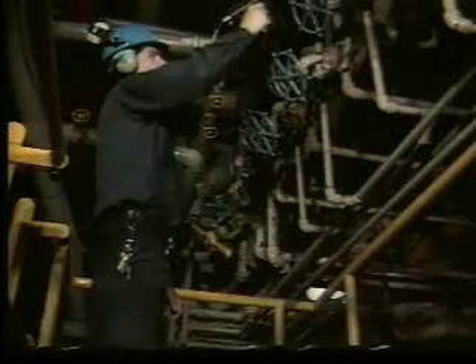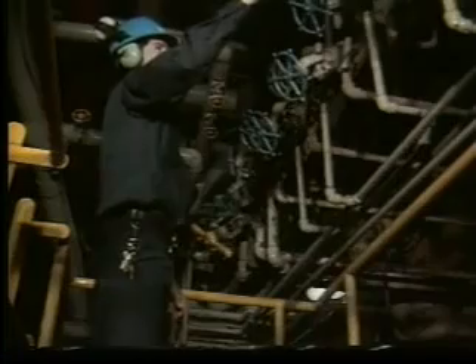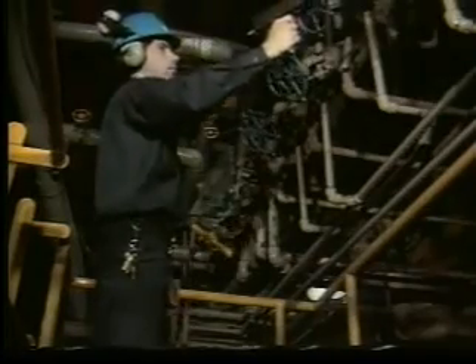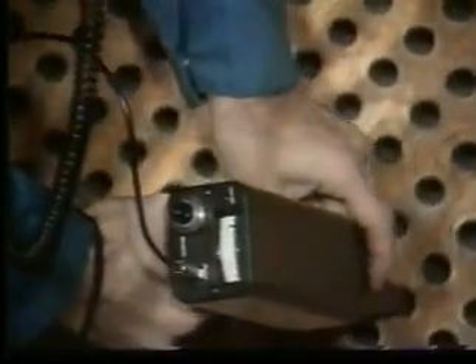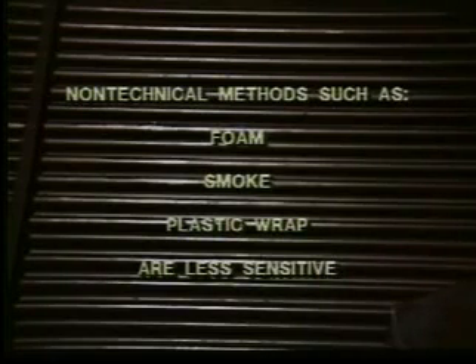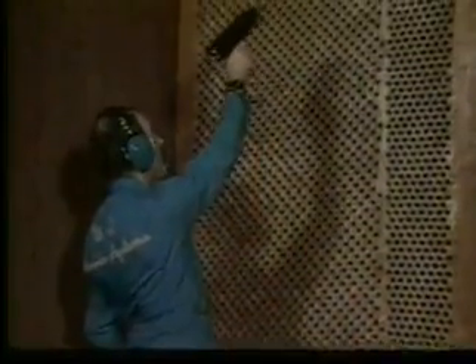Use the scanning mode of the ultraprobe as shown earlier. Adjust the sensitivity to move from gross to fine sounds, and move back and forth to confirm the leak site. Ultrasound is more frequently the method of choice for testing the integrity of condenser tubes while the condenser is at partial load. Other non-technical methods, such as using foam, smoke, or plastic wrap, are far less sensitive, and the more sensitive helium method is time-consuming. Ultrasound is fast and accurate.